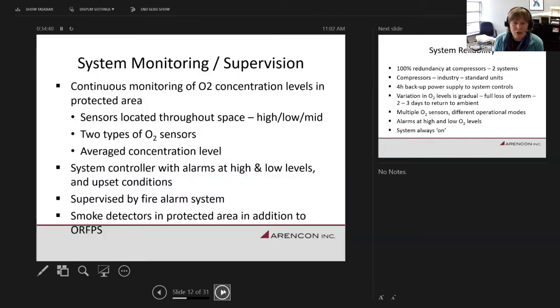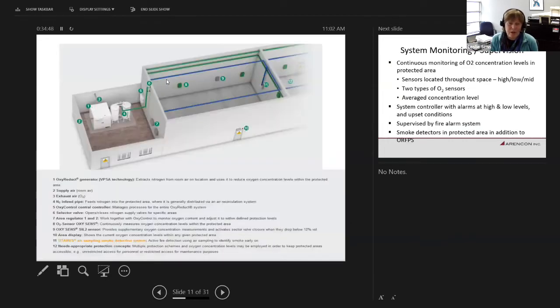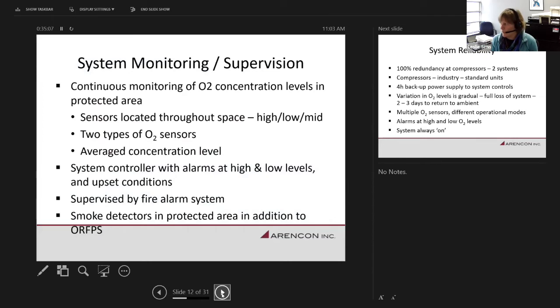So to make sure the system's working, there's obviously lots of monitoring and supervision because, if you come back to here, there's not a lot to see. We've got maybe 2-3 pipes coming into the space. When you're used to seeing sprinklers in a space and all the piping, it's very visual to see where the protection is. This is an oxyreduct. There's no sense of where the gas is. You're reliant on the sensors.